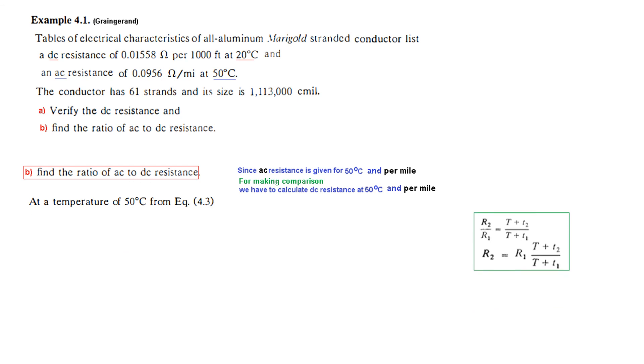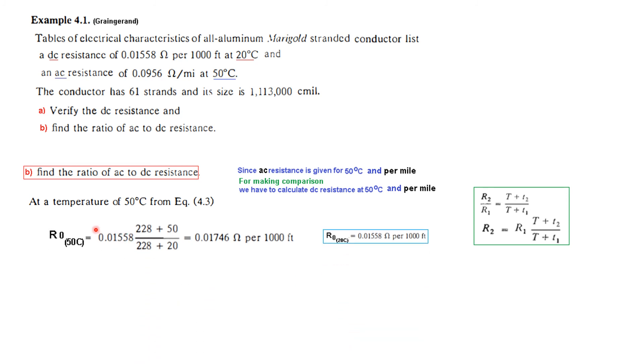For that we will use this formula here, and we will now calculate the resistance at 50 degree. We have already calculated resistance at 20 degrees, so we will use that. This was the resistance calculated at 20 degree. Capital T we will be using 228 as I mentioned earlier from the table. Temperature 50 and temperature 20. And this is the value of resistance at 50 degree centigrade, but this is for 1000 feet.